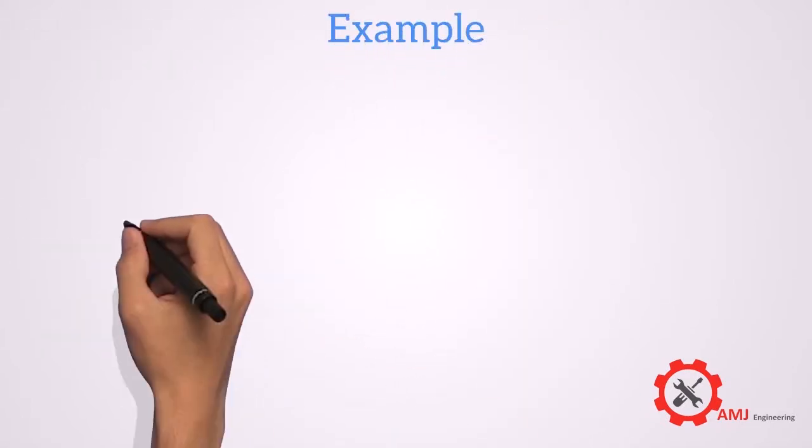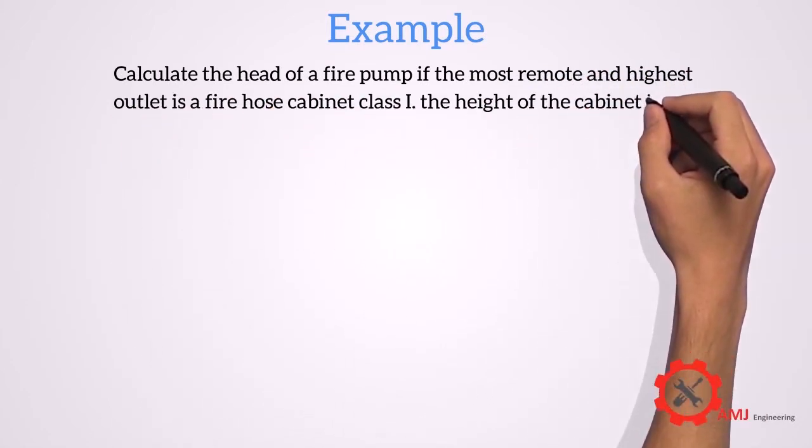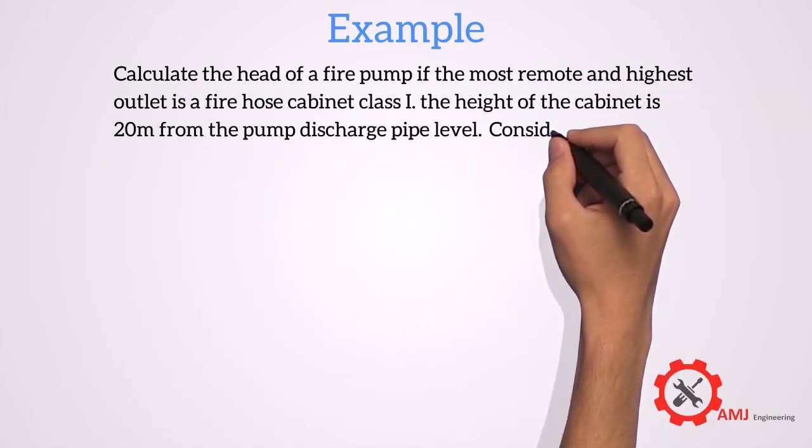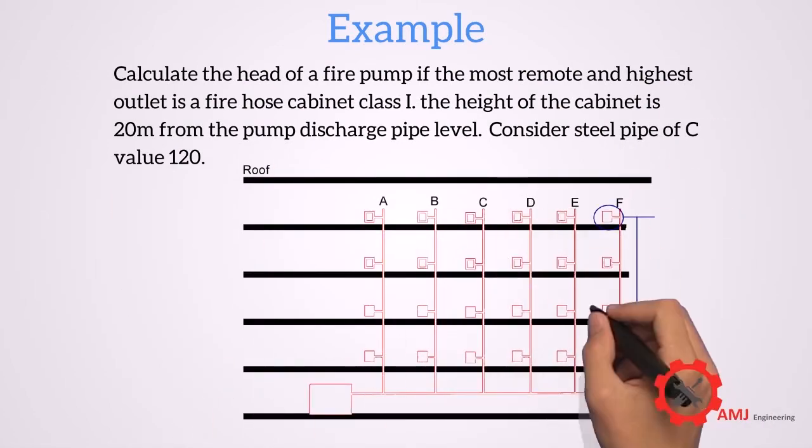Example: Calculate the head of a fire pump if the most remote and highest outlet is a fire hose cabinet class 1. The height of the cabinet is 20 meters from the pump discharge pipe level. Consider steel pipe of C value 120.